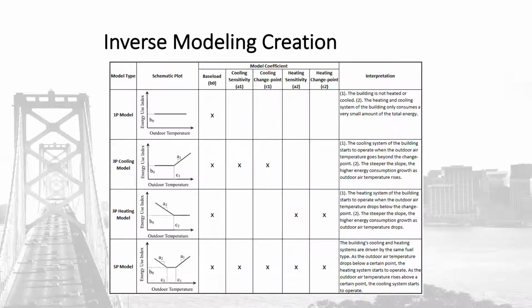Better can generate up to 5 model types: a 1-parameter model, a 3-parameter cooling model, a 3-parameter heating model, and a 5-parameter model. If you're familiar with the ASHRAE Inverse Modeling Toolkit, you'll understand that these plots and the coefficients within the models themselves can be interpreted to understand the performance of different systems and equipment in a building. So I'm going to take the example of the 3-parameter cooling model, which is the second model from the top.